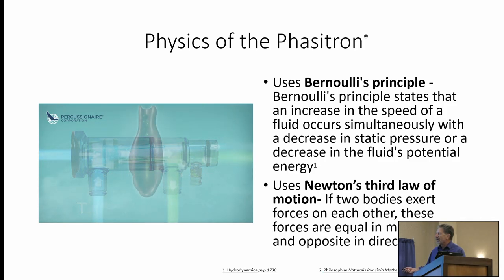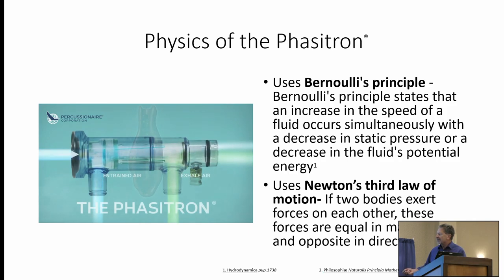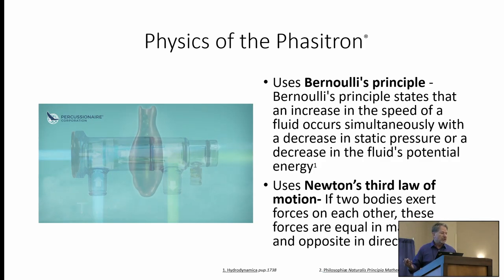Instead of pushing more gas into the patient's lungs, it actually exits through this port, which is normally an entrainment port. So when you're doing a therapy, unless you put extreme settings into the IPV device, it automatically adjusts pulse to pulse to the resistance or what is going on in the patient. It's not going to give them a large breath, even though when you first start to take a treatment it kind of feels weird, and most often people think, oh, it's going to pop my lung, until they relax and realize it's not. Because of this, it's not going to overinflate the lung.